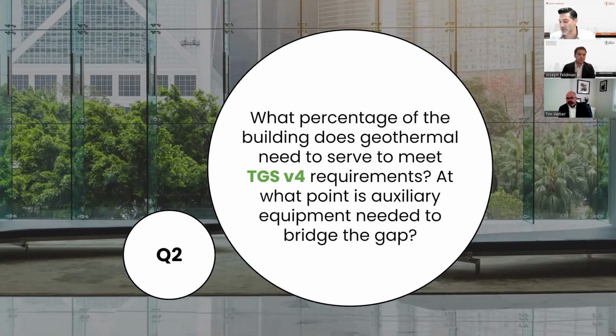As a percentage of the total load, the answer, roughly speaking, with the assumptions we normally take as true, is that you'd need a plant that's around 40-50% electrified at peak, which would capture 70-80% of your annualized heating. From a practical perspective, there are lots of geo jobs where it makes a lot of sense for other reasons for the geo system to serve 100% of your HVAC heating and cooling loads. So I'd say the majority of jobs we have under construction, or planned and going through municipal approval, may do future versions of TGS, and there are other programs we can discuss. But the majority of geothermal jobs that are occupied and operational, or well under construction, are the latter case.